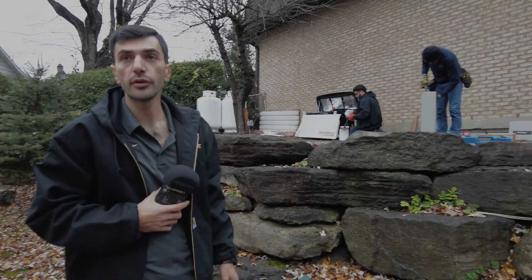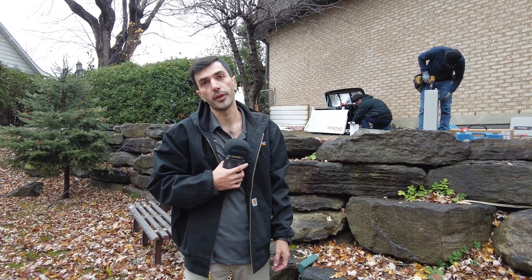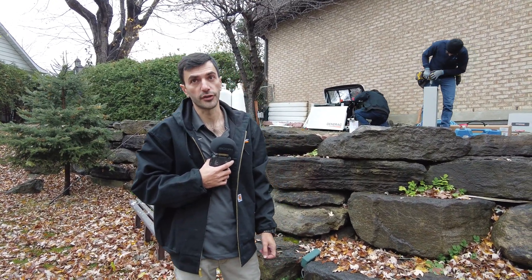We're doing another 26 kilowatt generator for the whole house. The heating system is electric and they have a hot water tank, so we are going to put a module on both of them to postpone the hot water tank and furnace. The baseboard heaters are going to give heat to the house, and then after five minutes the furnace is going to work.